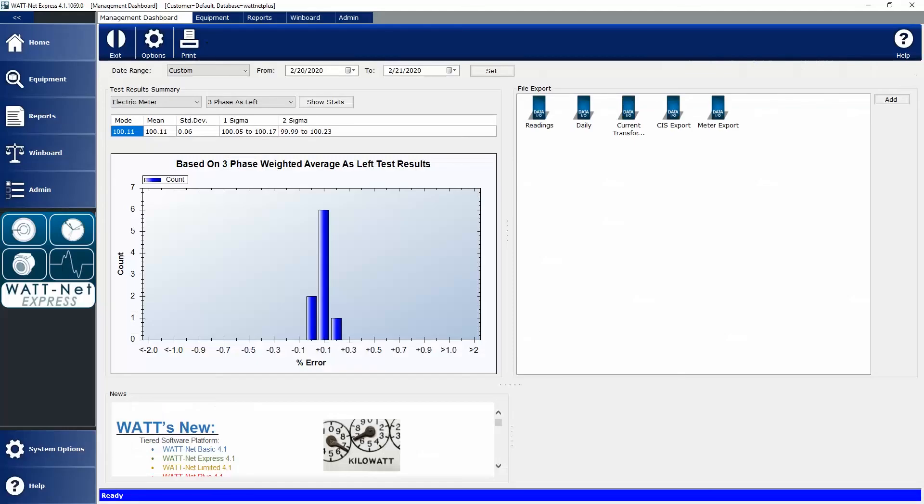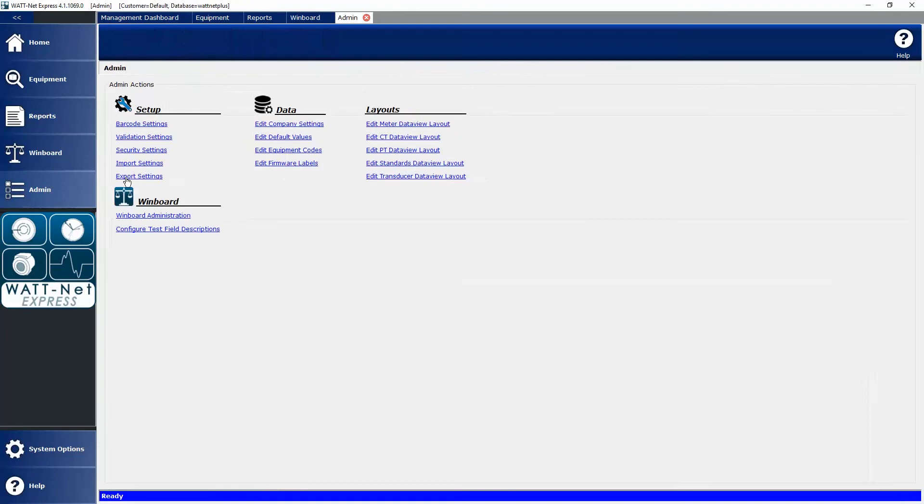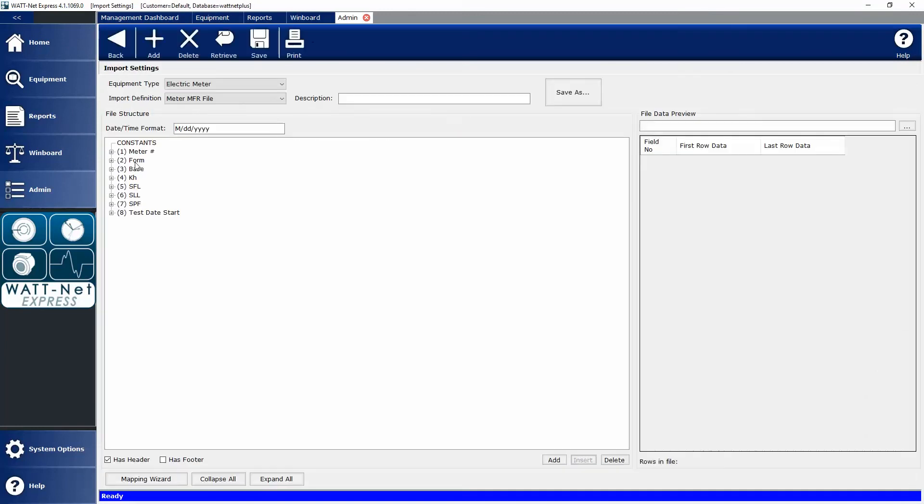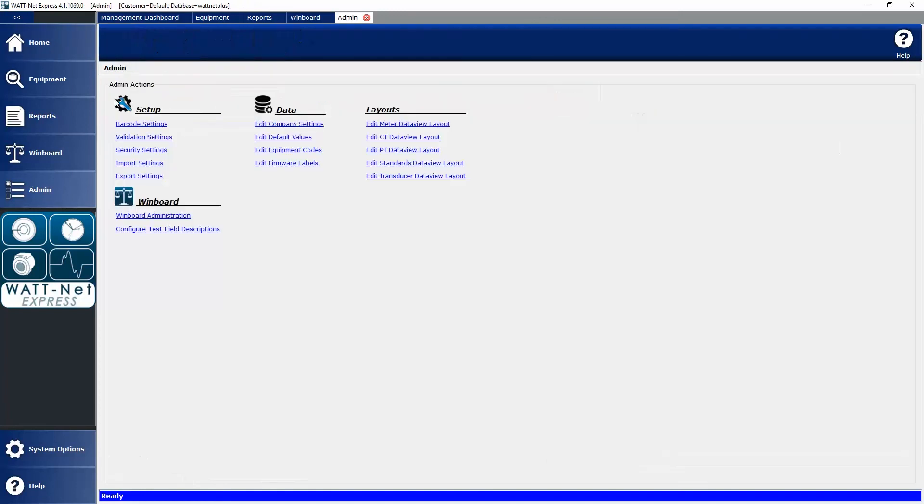When I go into my Wattnet Express software, I can easily import that. First of all, let's take a look at the import structure I created. In the import structure, you can see I've matched those same data points with my meter number, form base, pulse constant, my test data, and the test date. I also defined at the bottom that this one has a header row, so we need to disregard that first row. Then we defined our date format.